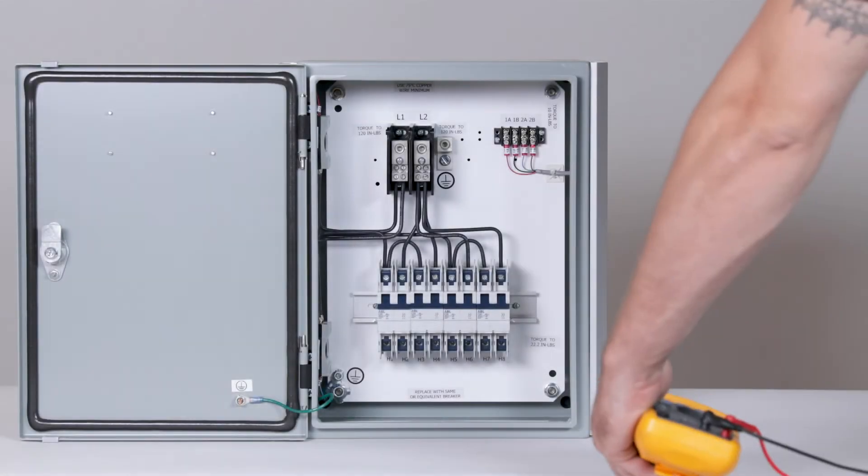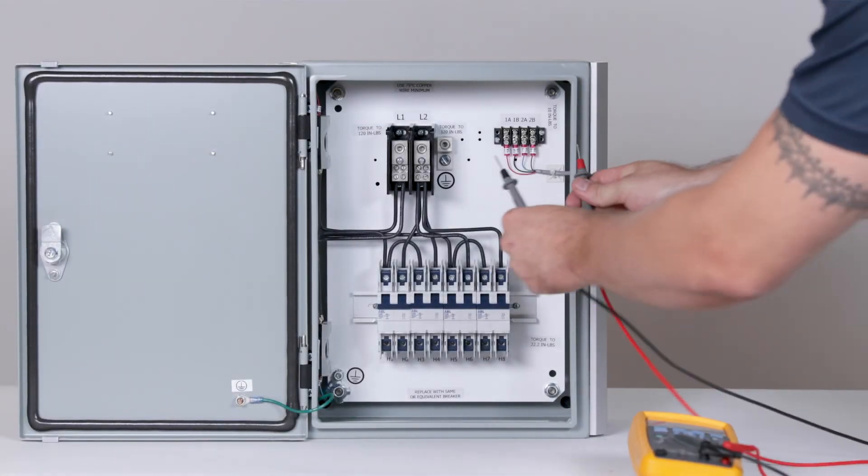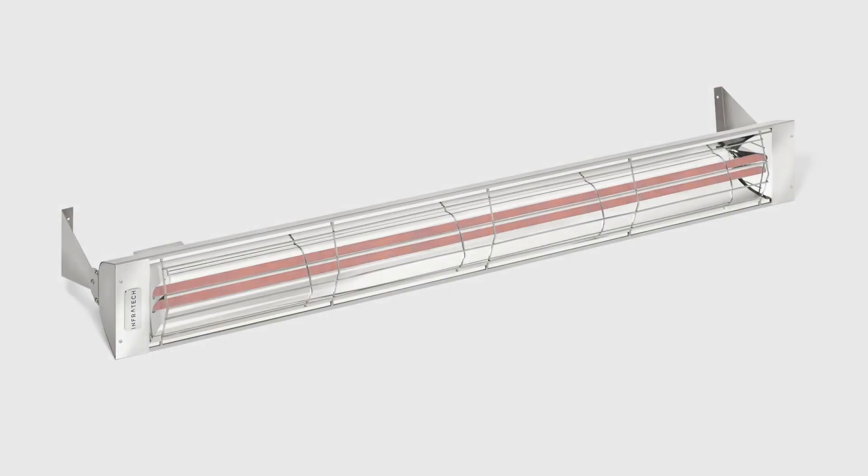Also, double check to ensure the polarity is correct by verifying that you have positive XA, negative XB. If everything checks out, you're all set. The heaters are now ready to operate.